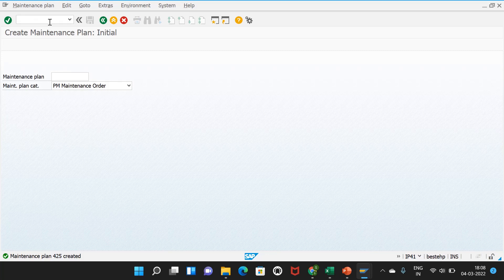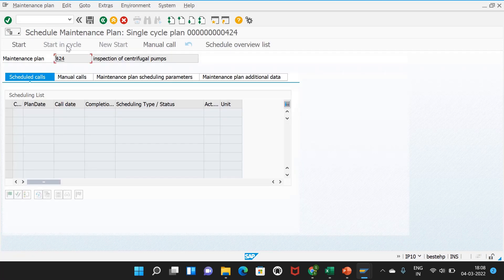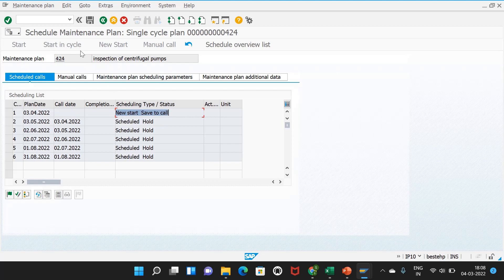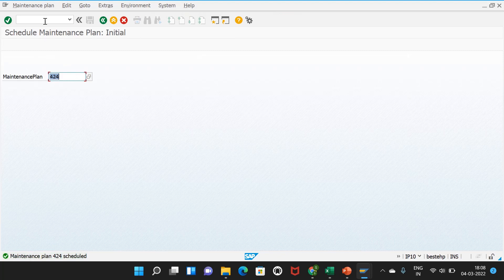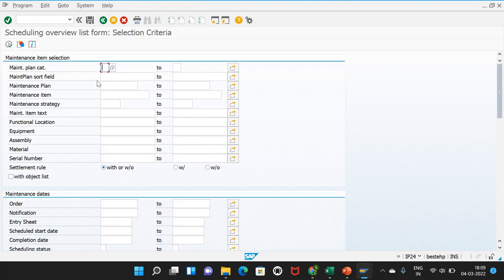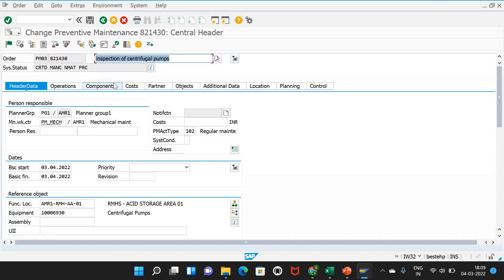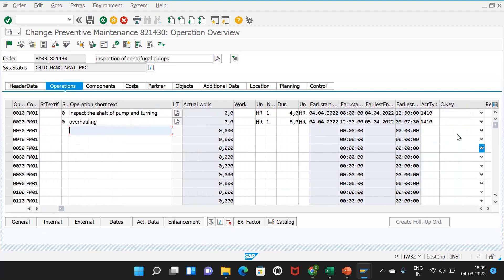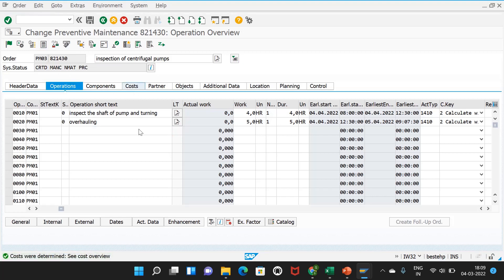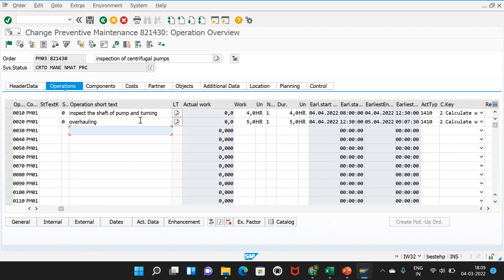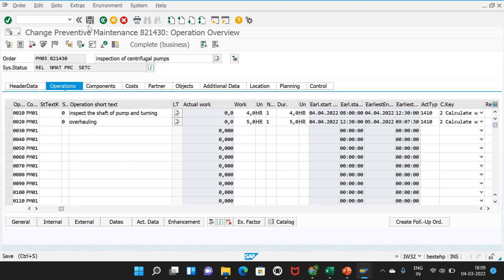Now I go to IP10 and schedule plan 424, which is for the centrifugal pump inspection. We save the scheduled plan. Then in IP24 for maintenance plan 424, we can see that one order has been generated — because the call horizon is 0%. I go to IW32, enter the order, go to operations, set the calculation key to calculate work, click enter, and the planned costs get generated. I then release the order and save it.